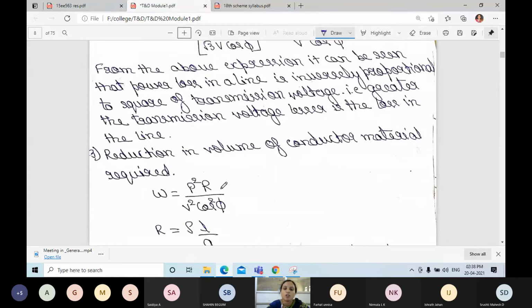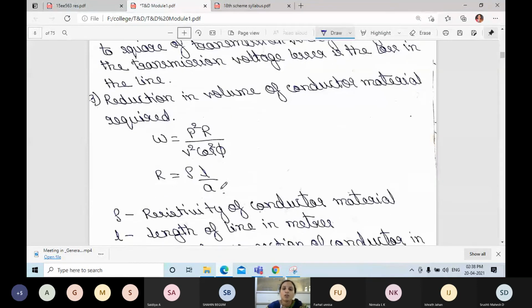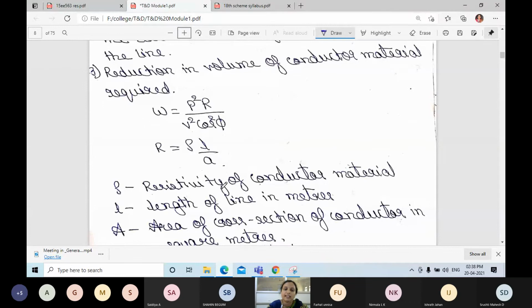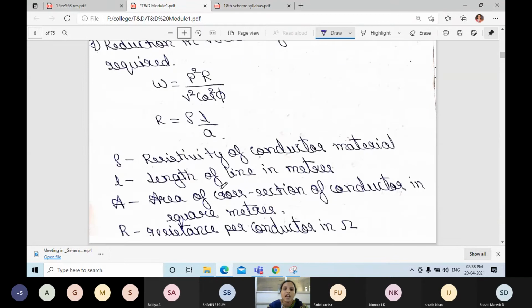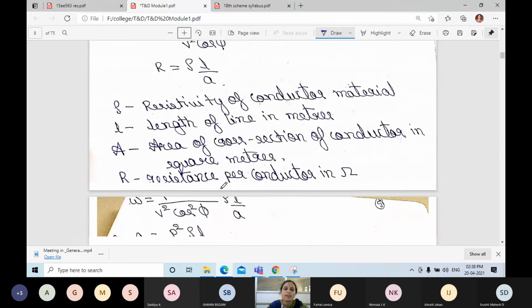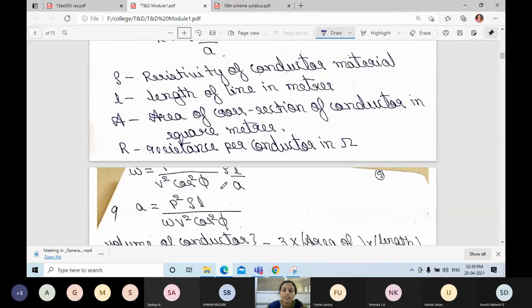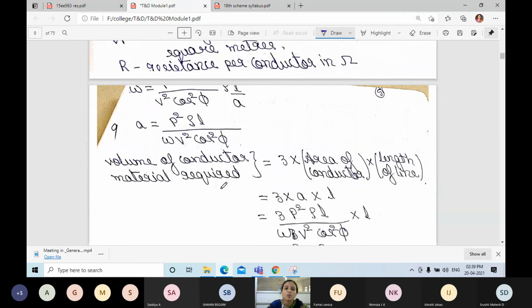Next is reduction in the volume of conductor material required. How will the volume of conductor material required be reduced? The formula is W is equal to P square R divided by V square cos square phi, where R is the resistance, R is equal to rho L divided by A. Rho is the resistivity of the conductor material, L is the length of the line in meters, A is the area of cross section of the conductor in square meters, and R is the resistance per conductor in ohms. The volume of conductor material required is equal to 3 into the area of the conductor into the length of the line.